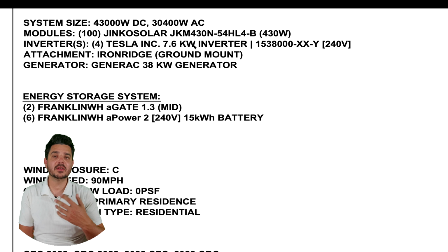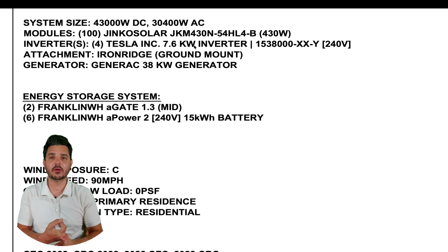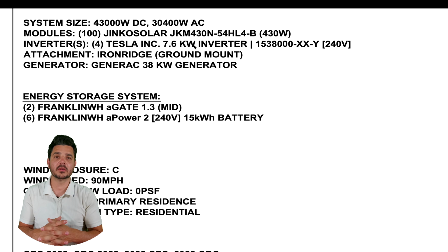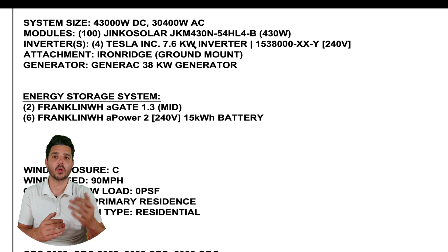Would I have liked to go with a little higher AC rating? Sure, but with microinverters, given the location of the equipment, it's 150 feet away from the batteries and the main electrical panel. I didn't really want to deal with that, and it's going to need a much larger wire size to get over there. And I think just speccing it out with the 430 watt modules, we weren't going to be able to back up the whole site, just because of how those microinverters work.